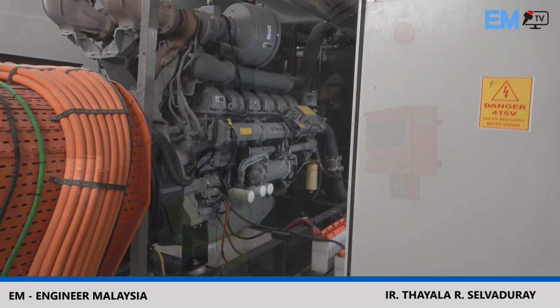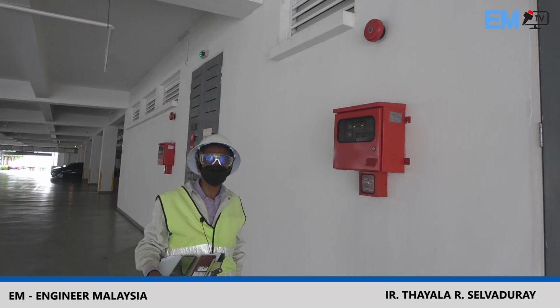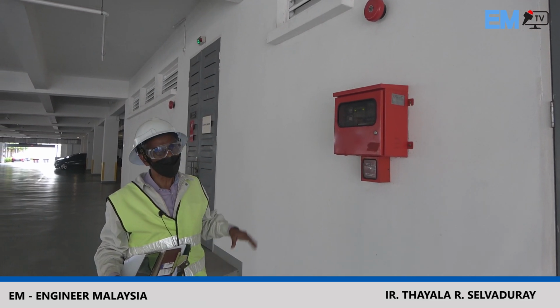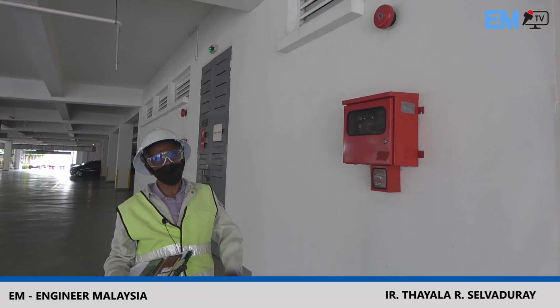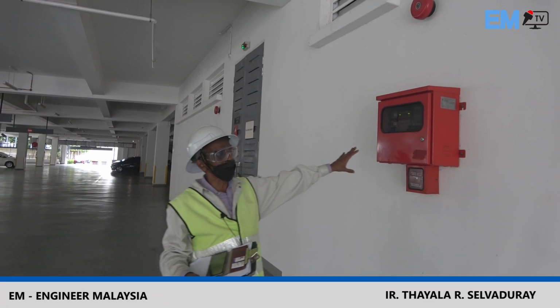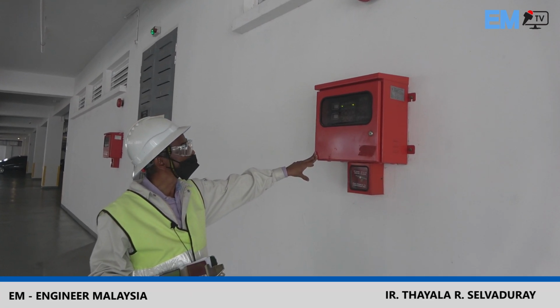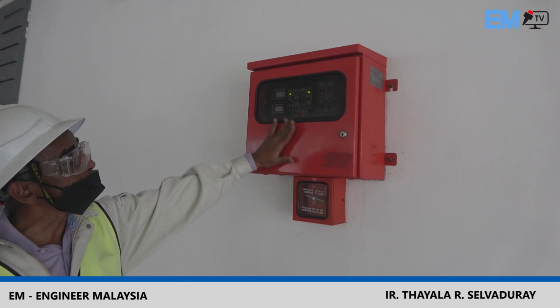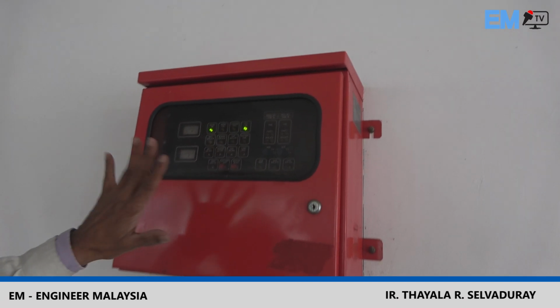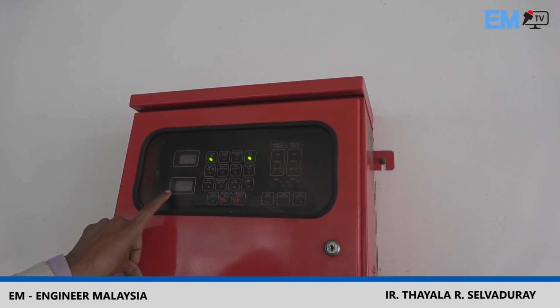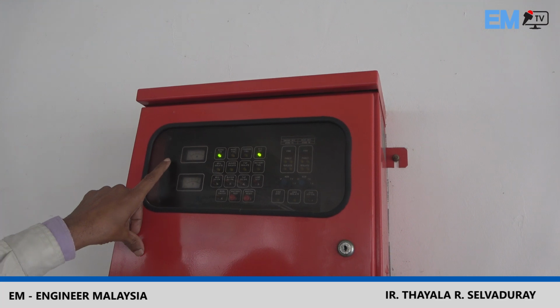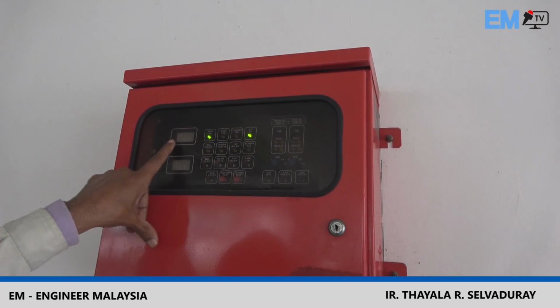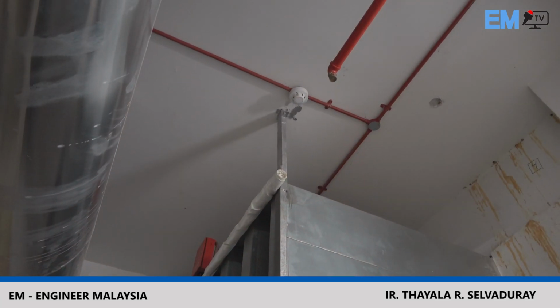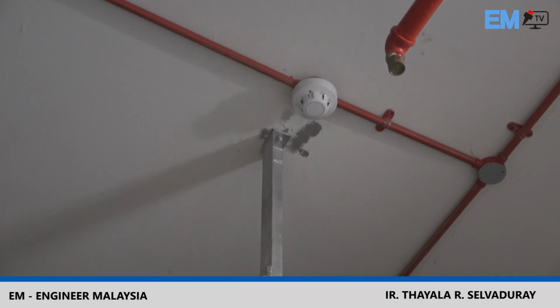Hi, let me also take this opportunity to share with you about the firefighting system in a typical electrical room. This is a panel which is located outside the door. It's supposed to say everything is healthy. So you see here a green light, that means it's okay. The voltage must be stable above 24 volts, and the battery must be on charge mode, and there are no alarms here. What you see up here is a smoke detector.